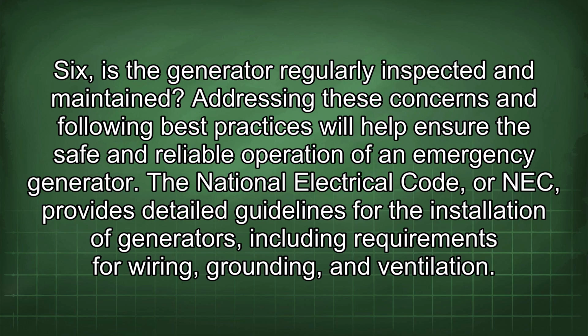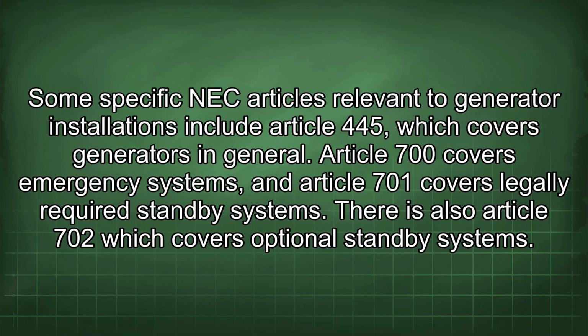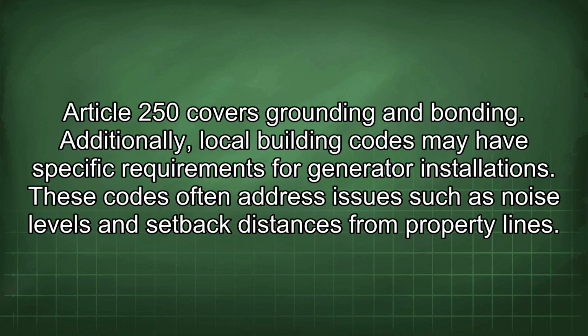The National Electrical Code, or NEC, provides detailed guidelines for the installation of generators, including requirements for wiring, grounding, and ventilation. Some specific NEC articles relevant to generator installations include Article 445, which covers generators in general. Article 700 covers emergency systems, and Article 701 covers legally required standby systems. There is also Article 702, which covers optional standby systems. Article 250 covers grounding and bonding.